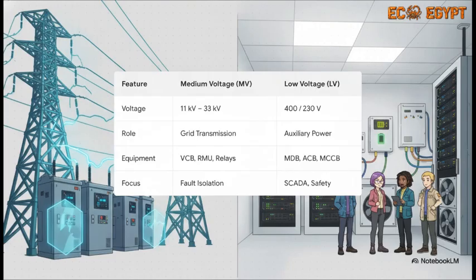Now, if we contrast the MV system with the low voltage, or LV system, you'll see two completely different operational worlds. While the MV side is handling that massive 11 to 33 kilovolt transmission to the grid, the LV system is operating much closer to what you'd find in a commercial building, around 400 or 230 volts. The LV system is super important, but it's really playing a supporting role. It's providing auxiliary power for local loads, things like cooling fans, battery chargers, and the SCADA servers. So to put it simply, the MV side is all about minimizing power loss and isolating huge electrical faults using heavy-duty switchgear, while the LV side is strictly focused on local safety and keeping the control systems running reliably.